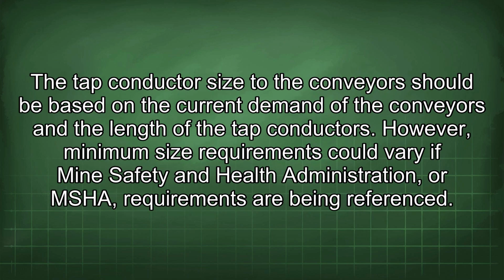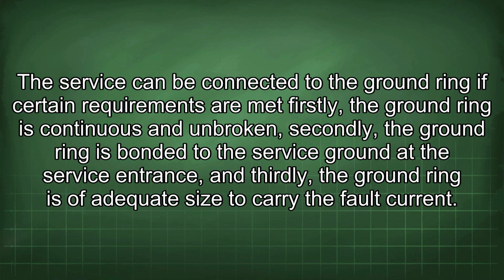The tap conductor size to the conveyors should be based on the current demand of the conveyors and the length of the tap conductors. However, minimum size requirements could vary if Mine Safety and Health Administration, or MSHA, requirements are being referenced. The service can be connected to the ground ring if certain requirements are met. Firstly, the ground ring is continuous and unbroken. Secondly, the ground ring is bonded to the service ground at the service entrance. And thirdly, the ground ring is of adequate size to carry the fault current.